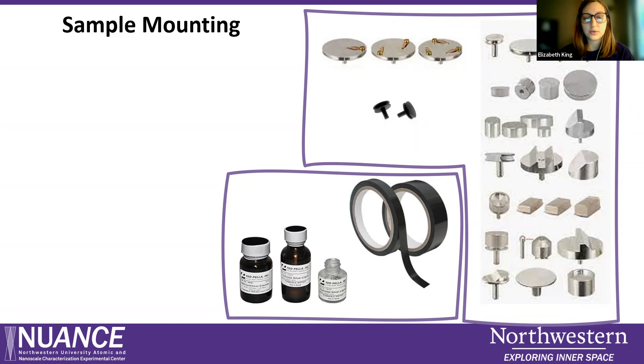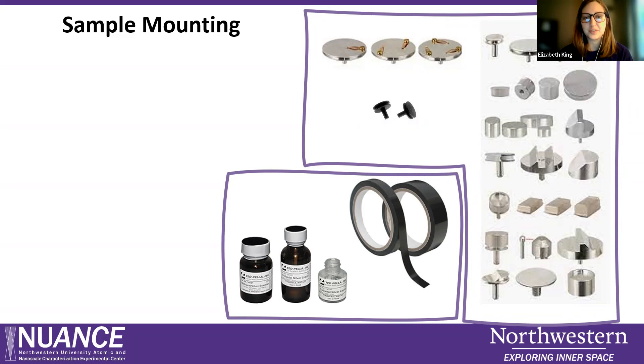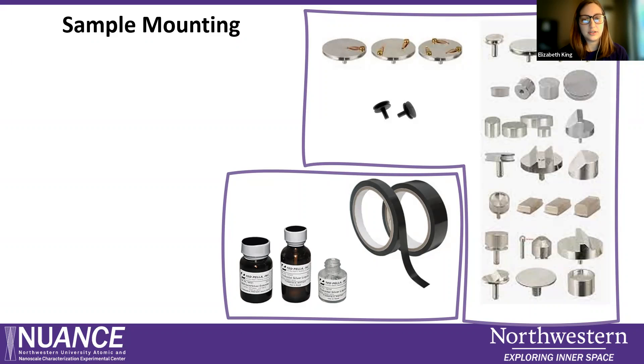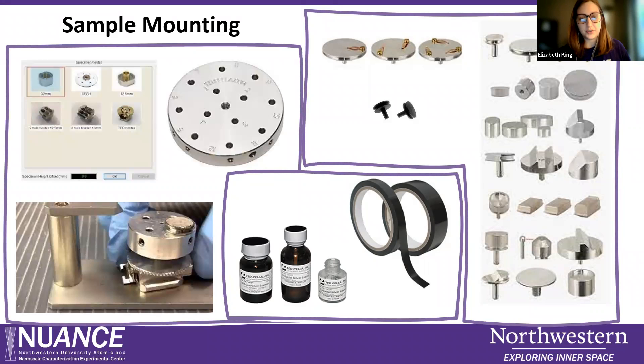There are two common types. On the right is carbon tape — it's a double-sided tape with carbon spheres throughout it that allow electrons to pass from your sample to the stub to ground. It's very easy to use and we have tons of rolls. On the left, we have these pastes that work almost like a little nail polish bottle, where you use it as a paint or a glue either to adhere the sample to the stub or to draw a conductive line from the top of your sample to the stub.